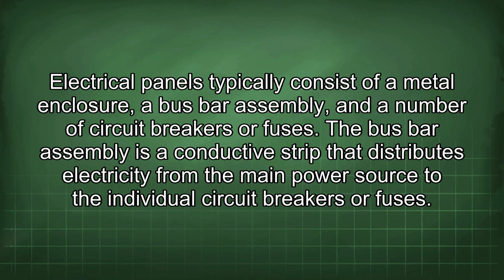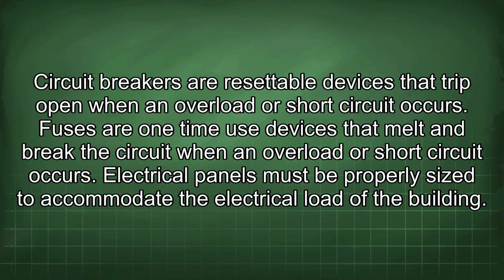Electrical panels typically consist of a metal enclosure, a busbar assembly, and a number of circuit breakers or fuses. The busbar assembly is a conductive strip that distributes electricity from the main power source to the individual circuit breakers or fuses. Circuit breakers are resettable devices that trip open when an overload or short circuit occurs. Fuses are one-time use devices that melt and break the circuit when an overload or short circuit occurs.